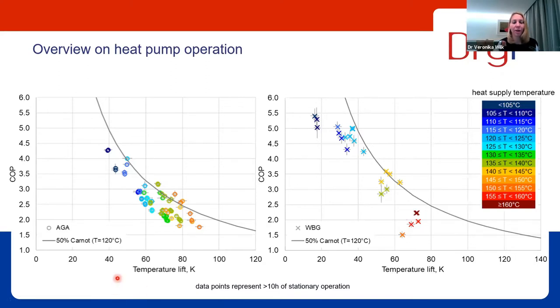With the Agrana demonstrator, we have tested a big range of operation conditions. Compared to the Wienerberger installation, we have operated this one at higher temperature lifts. This is mainly due to the colder heat source that we had available. And at a temperature of 138, it's very close to the design point of the heat pump, we have a COP of 3.2, and that's that one. That's a very, very good operation point. We have tested several different conditions for the high temperature side. Those are the orange and red ones, but also lower lifts where we have similar values as we've seen before. At a temperature lift of 40 K, we have a COP of about 4.2.